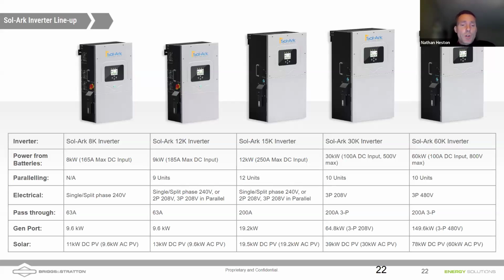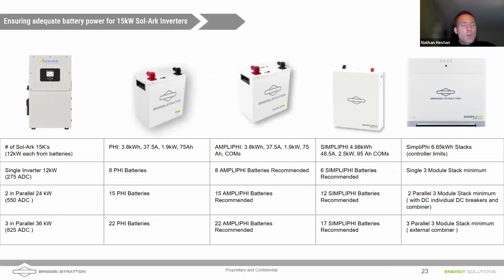We can also produce 208 with the 12k and 15k Sol-Ark inverters. And so if you're interested in 208, you can do 2 legs of 208. So if you're in a shop like mine that has 208, you can do 2 legs of 208, take in 208 power. You can do balanced 3-phase with 3 inverters. So if you're going to feed back to the grid, you'll need to do balance. But you can do those with the low voltage inverters as well.